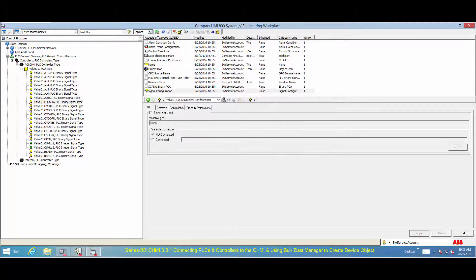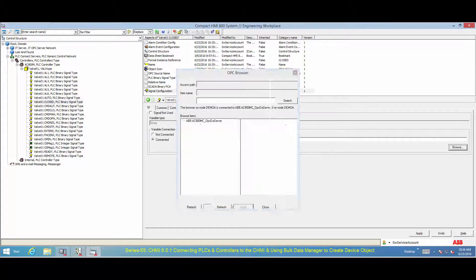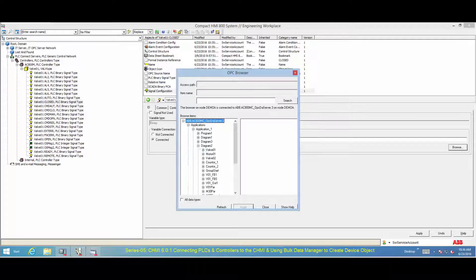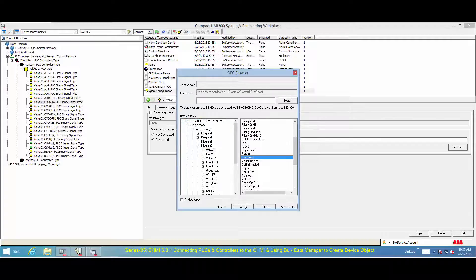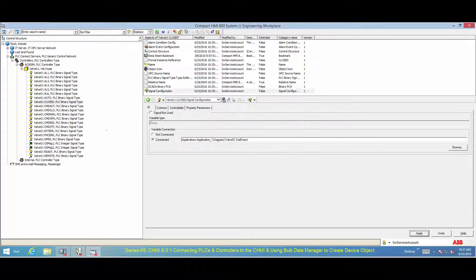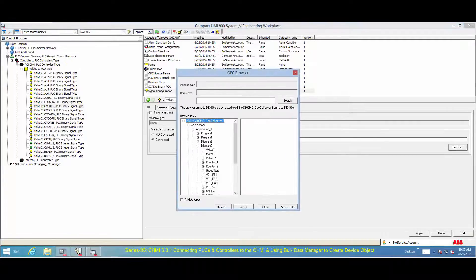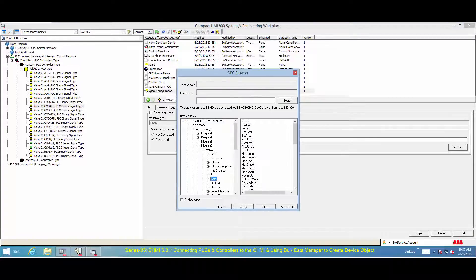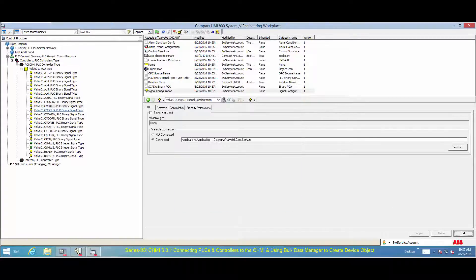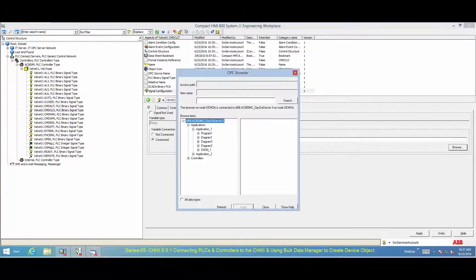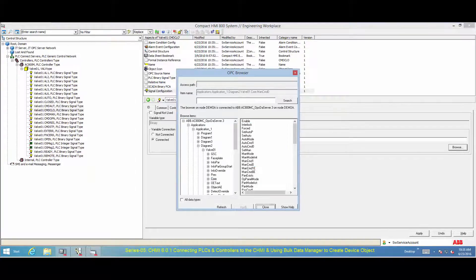Repeat the same procedure for configuring each signal. Please note that the Browse function is only available if the OPC server supports browsing. A signal can also be connected by adding the address string for the property.